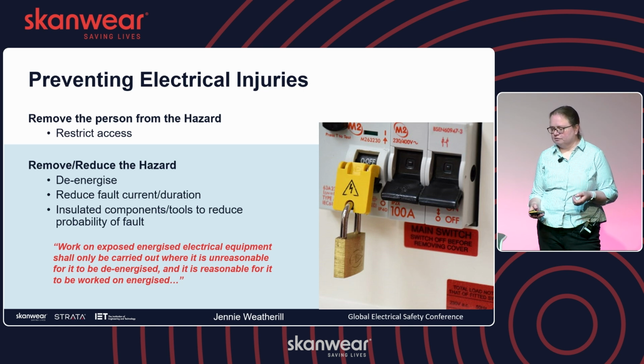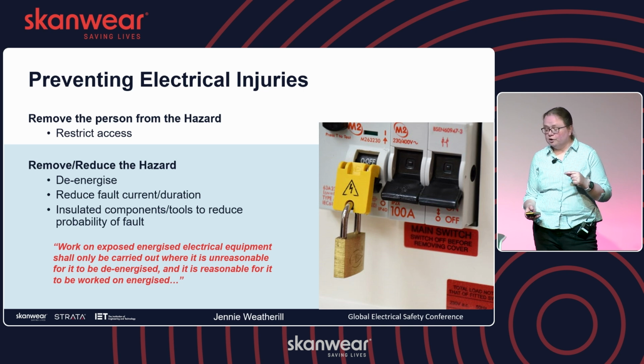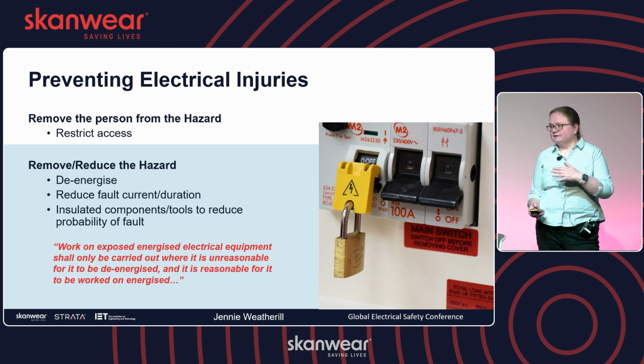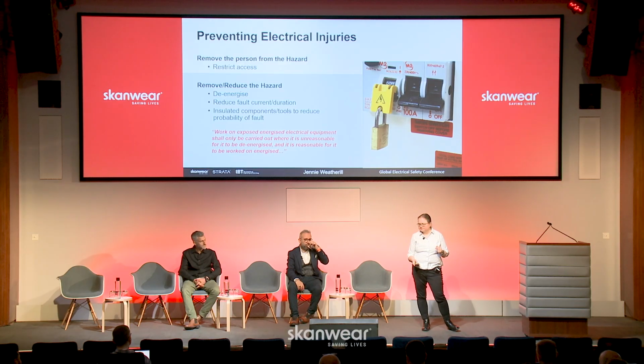This is pulled out of our safety rules. I think there's very similar wording in many other people's safety rules. Work on exposed energized electrical equipment shall only be carried out where it is unreasonable for it to be de-energized, and it is reasonable for it to be worked on energized. So this is where you come in: I can't do a phasing check if it's dead. That is a reasonable reason to work on it energized. The fact that I want to save half an hour is not a reasonable reason to work on it energized.